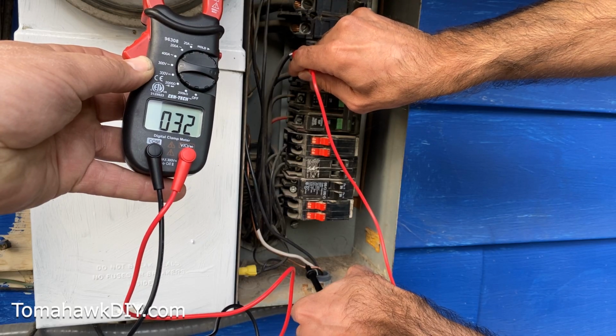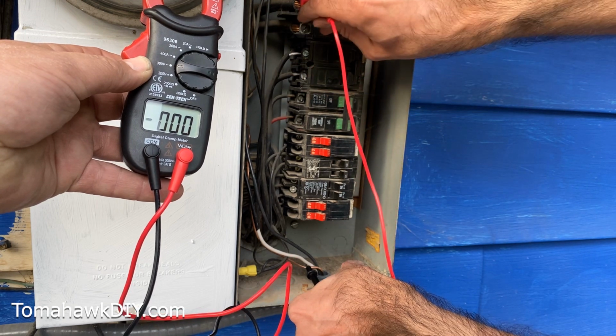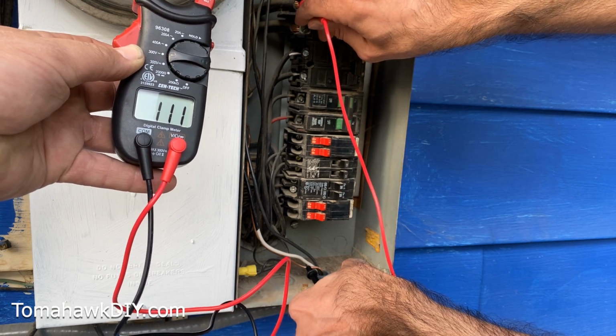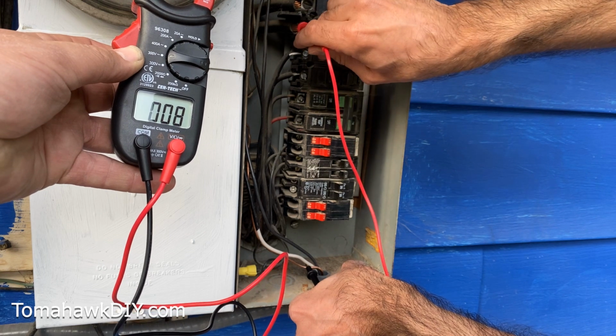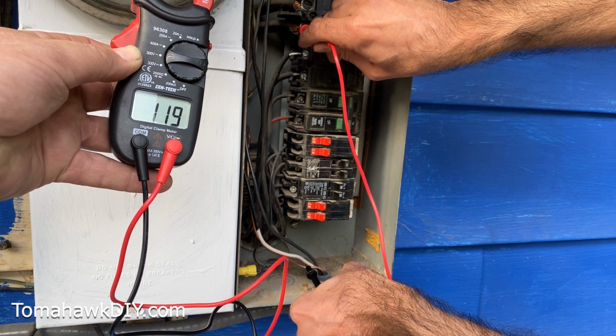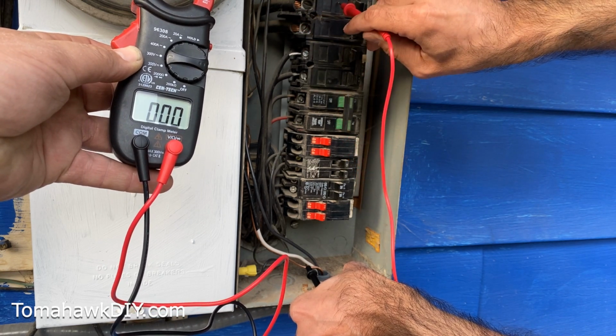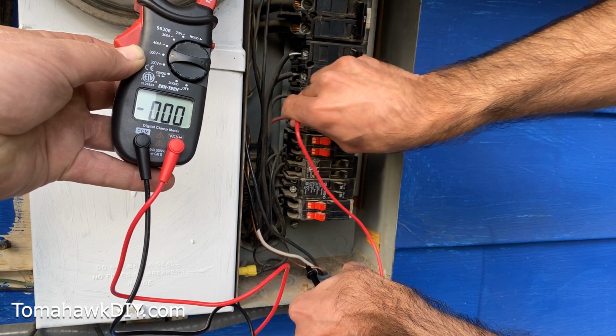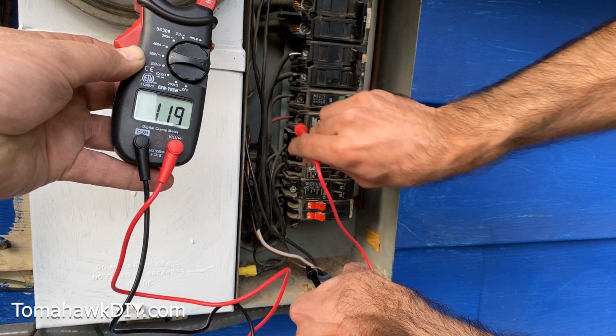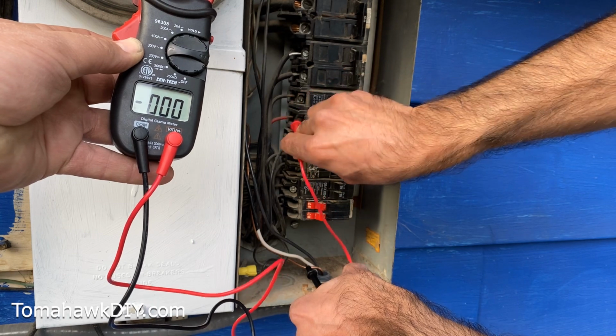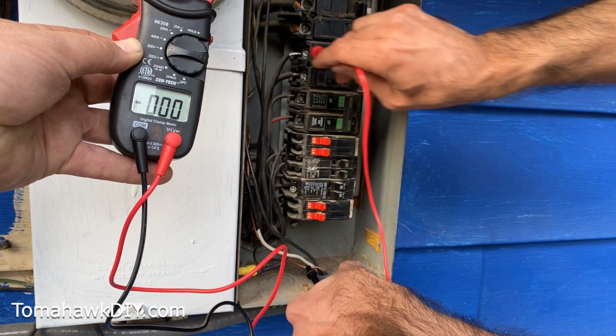That suggests there's a problem with this. With our incoming power, if we check that, we've got 119 here, 119 there, so incoming power is good. We could check other breakers as well, and we'll see those showing the appropriate power, but this leg's fried, so we got to replace this circuit breaker.